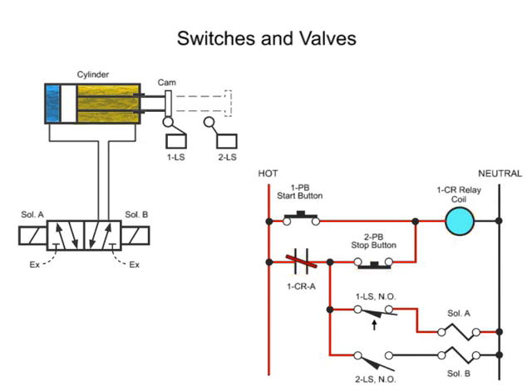This allows the relay to hold a circuit through the stop button and contacts 1CRA. Once the contacts are closed and connected, the coil will remain energized even if the start button is released. When contacts 1CRA are closed, electrical power is distributed to the rest of the circuit.